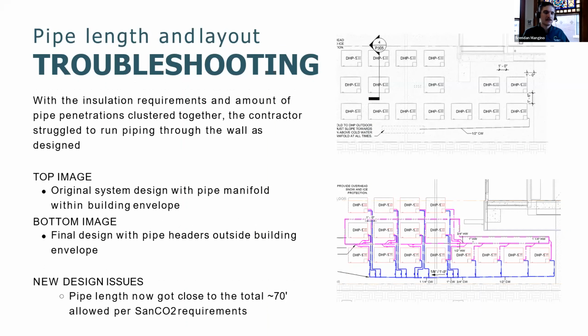Another thing we ran into was pipe length layout. Originally we were planning on penetrating the wall with a manifold that was inside and individual home runs outside the building envelope. This would have been 32 different pipe penetrations, and we found that just wasn't practical during construction. So we ended up converting it to 4 pipe penetrations, 2 supply, 2 return, and then headers running out to each heat pump. But since we're piping this in reverse return to get effective balancing without check valves or balancing valves, we got close to the maximum pipe length of the system.